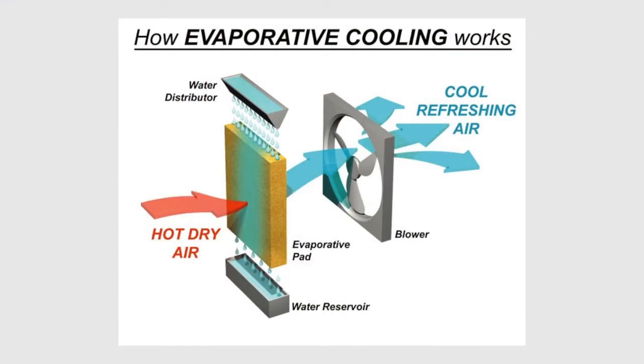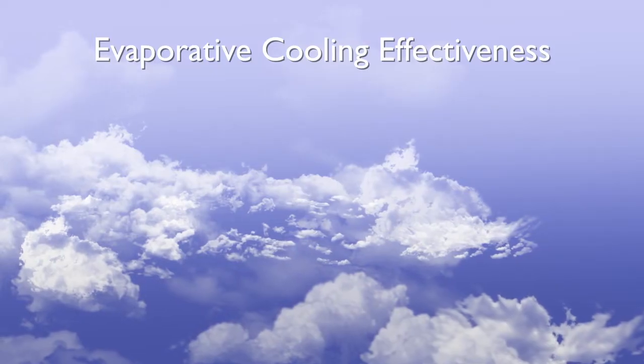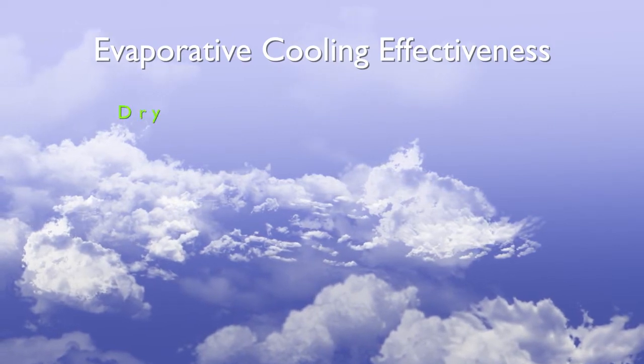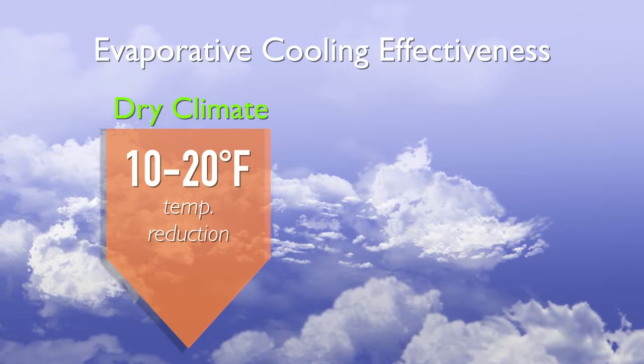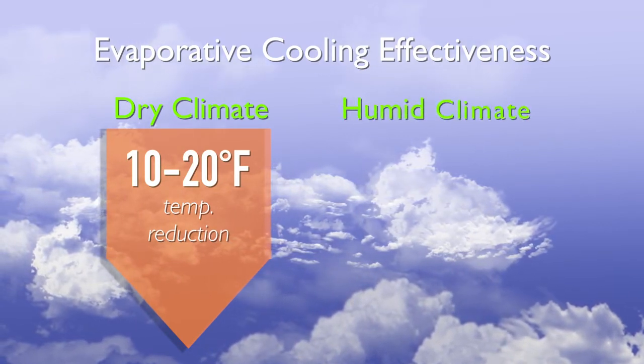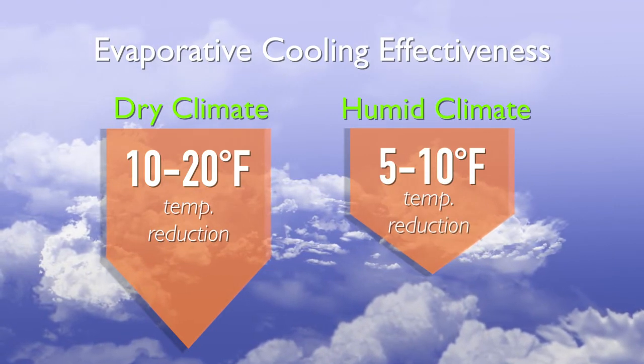This diagram shows how an evaporative cooling pad system works. A fan draws hot, dry air through a water-soaked pad. As the air flows through the moist pad, the water evaporates, taking heat out of the incoming air. Evaporative cooling is more effective in drier climates, where it can reduce temperatures by 10 to 20 degrees Fahrenheit. In more humid climates, the temperature drops are closer to 5 to 10 degrees Fahrenheit.